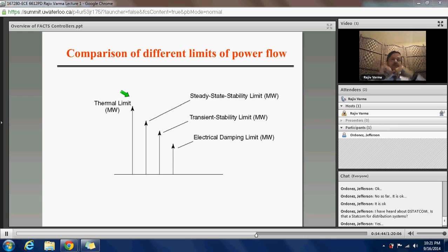There has to be a minimum clearance distance from the ground, and the maximum power that can flow in a line so that the sag is not more than a particular limit is known as the thermal limit. And people monitor the maximum power flow in a line at the Windsor Detroit crossing. They have video cameras, and they keep recording the sag of the line. They tell you how much power is flowing, which is very interesting. So thermal limit is the maximum power that you can send on a line from heating constraints.